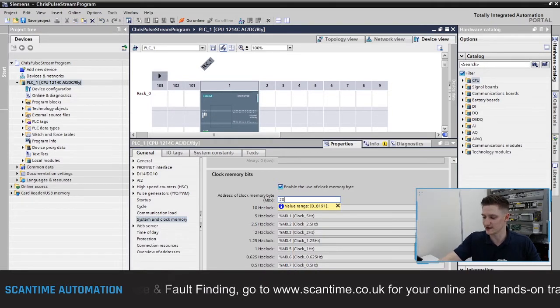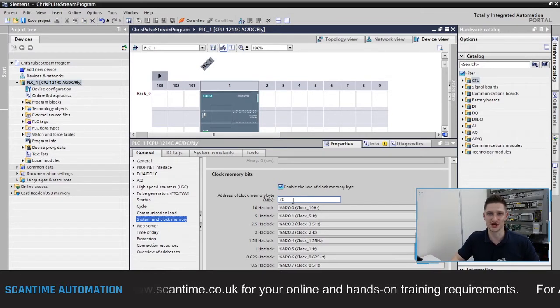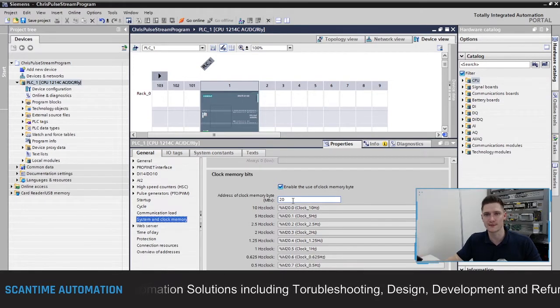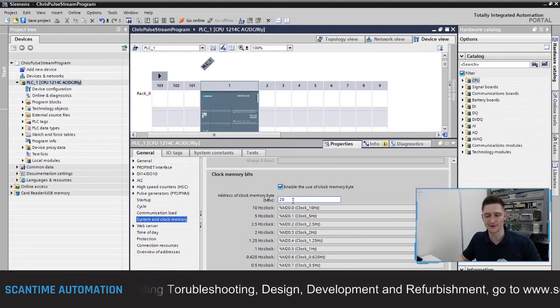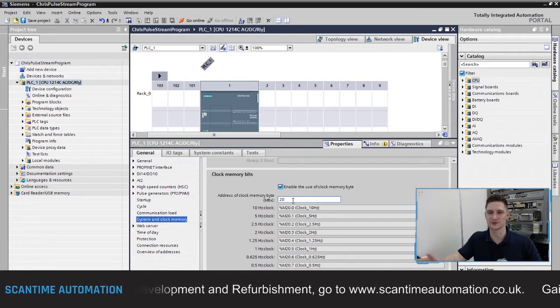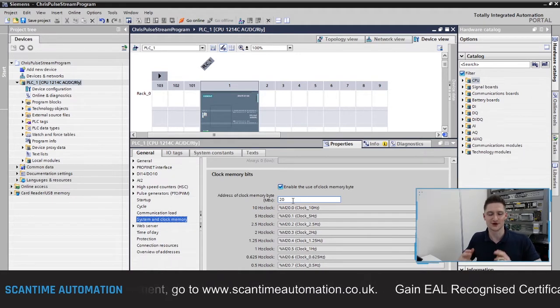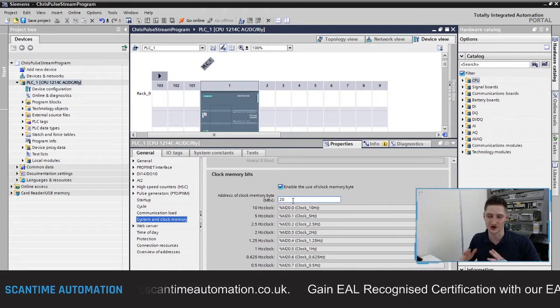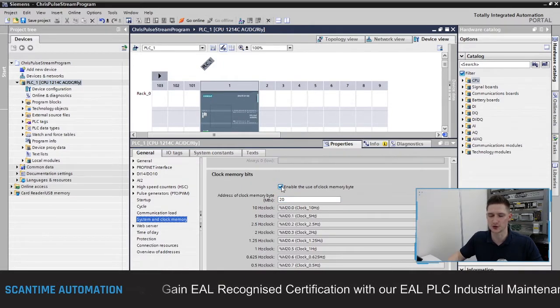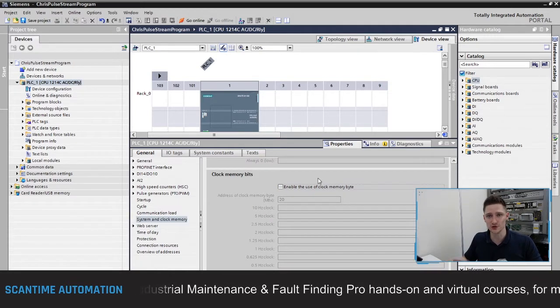You can change the clock memory byte — just click inside the box, type another value such as 20, and press Enter; the bits will update accordingly. Be careful not to assign it to a memory byte already used in the program, otherwise outputs could flash on and off unintentionally. I'm going to leave this unchecked because we're not going to use the clock memory — we're going to show you how to create a pulse stream using ladder logic instead.